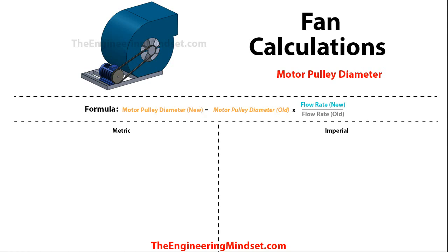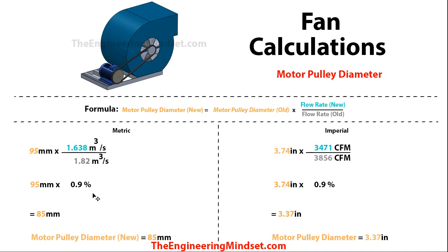If there has been a change in flow rate and you need to know the new motor pulley diameter, use this formula: new motor pulley diameter = old motor pulley diameter × (new airflow rate ÷ old airflow rate). Dropping in the numbers — the airflow rates cancel to give a ratio — and multiplying by the original pulley diameter gives a new motor pulley diameter of 85 mm (3.37 inches).